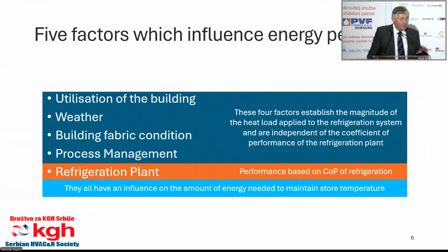They all have an influence on the amount of energy needed to maintain the store temperature at the desired value. And that's a key metric that we perhaps have misunderstood over the years. You know, if the room is cold enough, then everything is okay. Not necessarily true. The room might be cold enough and the energy bill is through the roof. So we need to be a little bit more intelligent about analyzing the information than that.